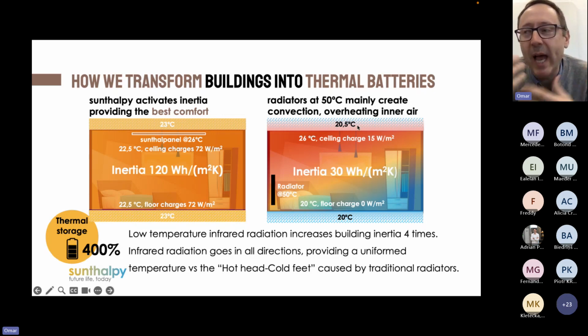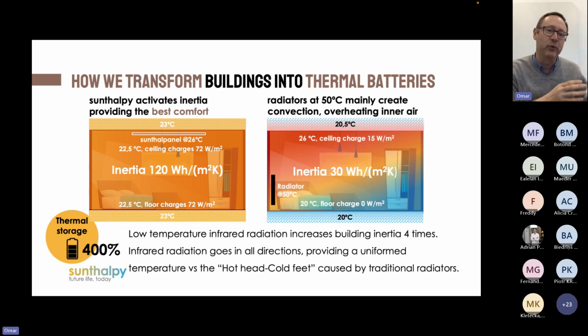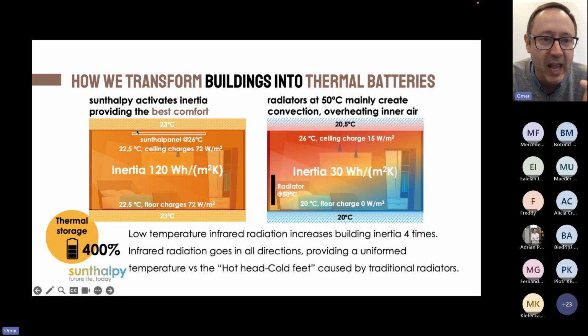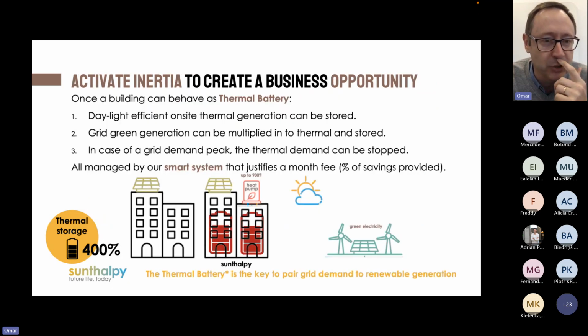So in order to heat up the mass, the structure of the building, we have to keep working continuously and at high temperatures, inefficiently, to be able to heat up that mass. However, if we work at low temperature with a high surface element radiating, we are able to heat up our structures and furniture, multiplying by 4 the activation of the thermal mass of the building. This is very important because it gives us the opportunity to actually convert the building into a thermal battery.